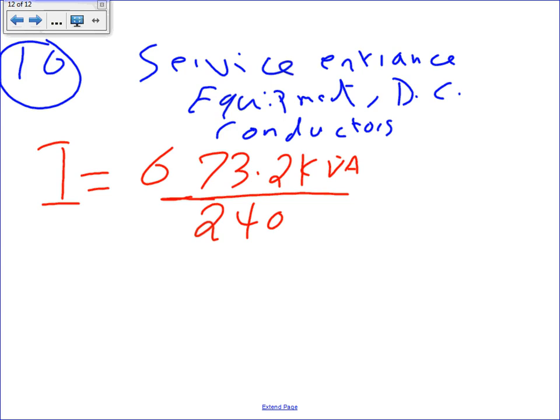So I have 240 volts, right? This is my volt, and don't forget to convert the K. What's the amp? Two people to agree on 1 amp. Now round up to a whole number here. Approximately 2.8K, and we don't want K. When we move into the amps, we're going to get rid of the K. 2,805 amps. Anybody came up with something similar, close? Okay. 2,805 amps.